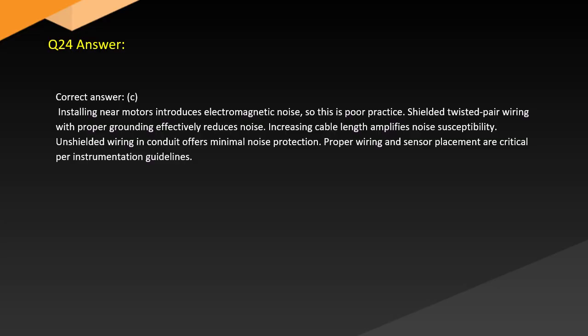Answer. Correct answer. C. Installing near motors introduces electromagnetic noise, so this is poor practice. Shielded twisted pair wiring with proper grounding effectively reduces noise. Increasing cable length amplifies noise susceptibility. Unshielded wiring in conduit offers minimal noise protection. Proper wiring and sensor placement are critical per instrumentation guidelines.